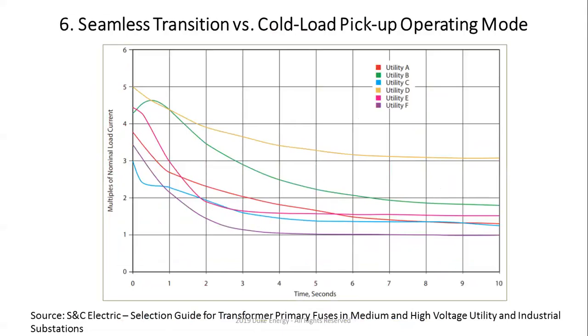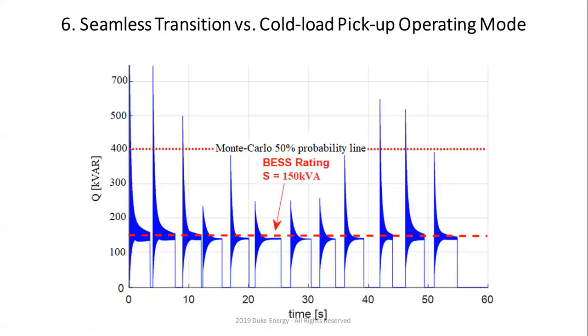So as you can see, when you try to do cold load pickup, it's much more challenging to pick it up, right? This is, again, different utilities that have shown what their inrush currents are as a function of time when you have to do cold load pickup. And again, that's a function of whether you are doing cold load pickup 5 seconds, 2 minutes, or an hour after your main grid was lost, right? So let me just tell you what I did. I did a generic implementation for a generic microgrid with 100 kVA PV and 150 kVA battery. And I tried to see what it takes to do the cold load pickup.